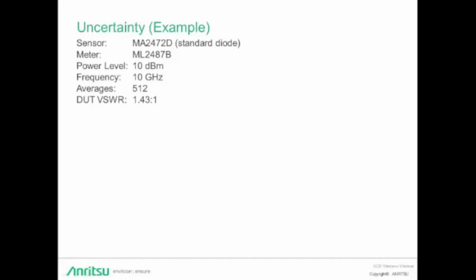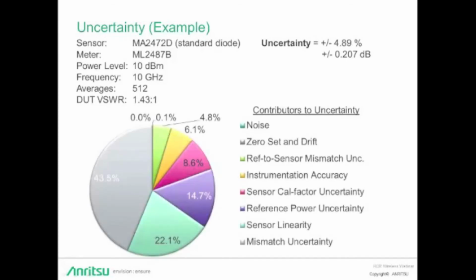Consider this example of an MA2472D standard diode sensor under the conditions listed. The uncertainty of the measurement is known as plus or minus 4.89% or 0.207 dB under these conditions. And here's our list of contributors to the overall uncertainty. From the chart, we can see mismatch uncertainty is the largest contributor by far in this specific example.